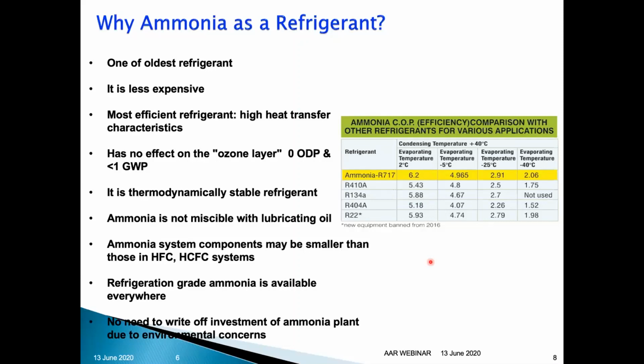So that can be almost around minus 0.6 kg per centimeter square gauge pressure, and typically discharge pressure depends on your water temperature, wet bulb temperature and condenser design. In India, condensing temperature can vary from 35 to 40 degrees. So pressure can be around 12.5 to 14.5 kg per centimeter square. That's totally your system design requirement, sir. Ammonia can work in a very wide temperature range. Okay, sir. Thanks for the informative session. Thank you, sir.